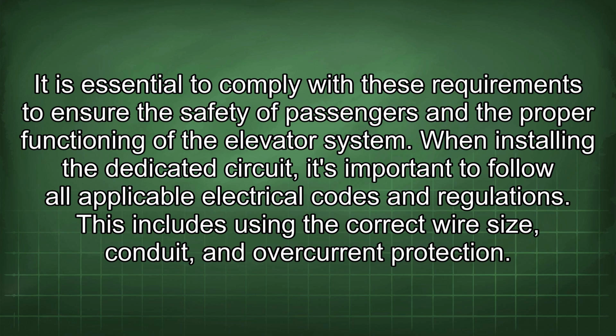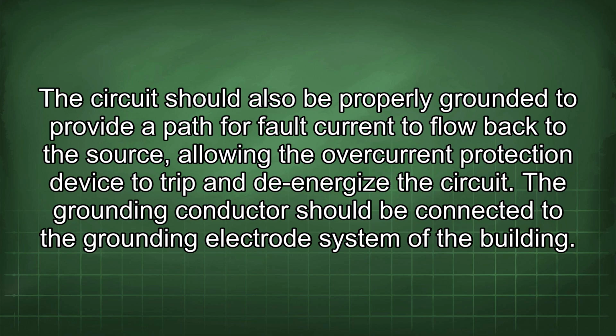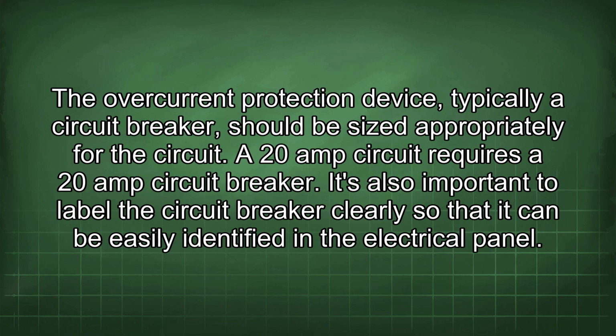This includes using the correct wire size, conduit, and overcurrent protection. The circuit should also be properly grounded to provide a path for fault current to flow back to the source, allowing the overcurrent protection device to trip and de-energize the circuit. The grounding conductor should be connected to the grounding electrode system of the building. The overcurrent protection device, typically a circuit breaker, should be sized appropriately for the circuit. A 20-amp circuit requires a 20-amp circuit breaker.